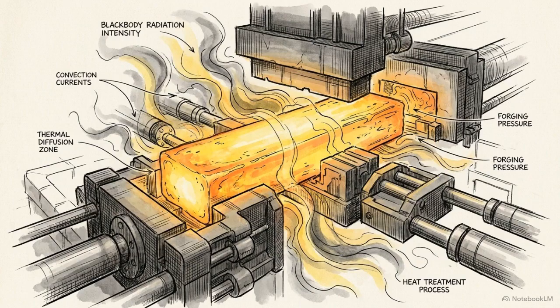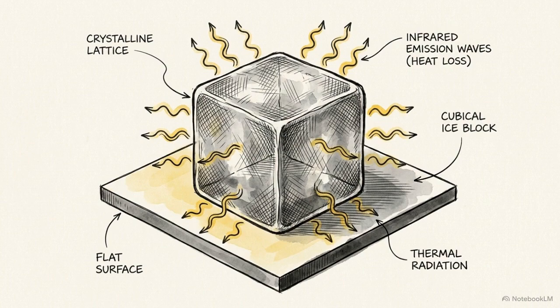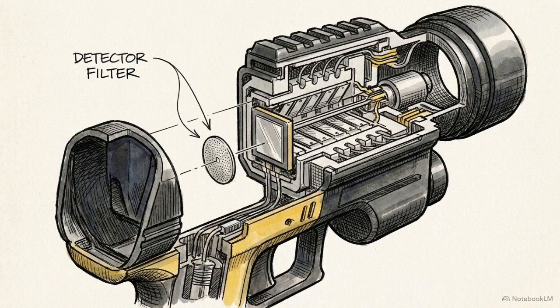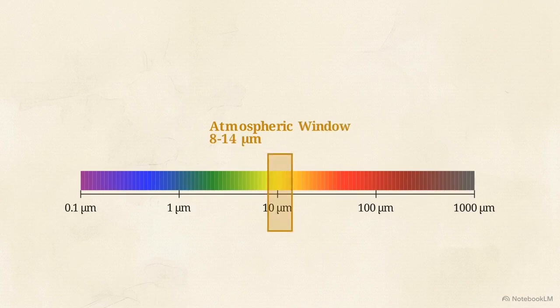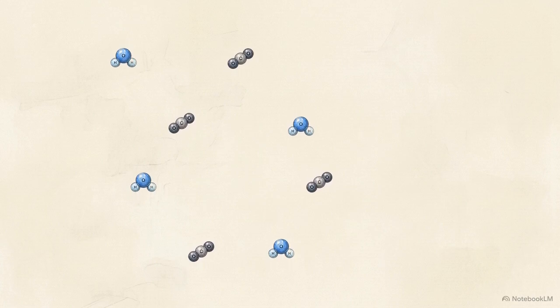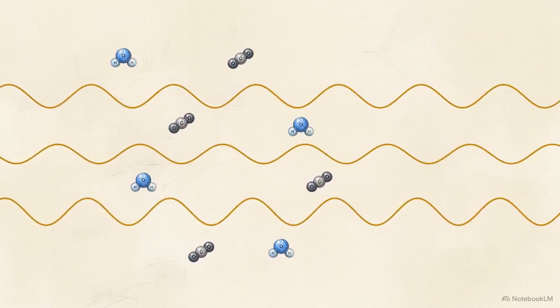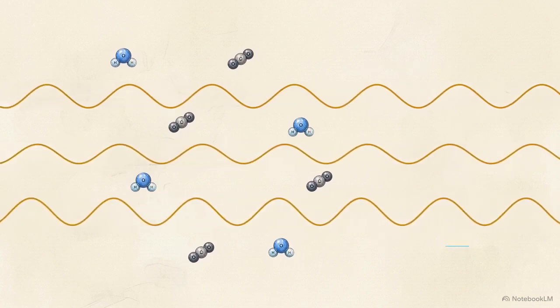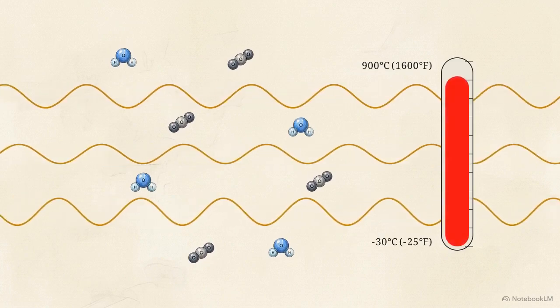At the sensor level, measuring that precise targeted zone requires strict adherence to the laws of thermodynamics, specifically the principles of black-body radiation. All objects above absolute zero emit electromagnetic radiation. To capture this, the MX6 utilizes a specialized thermopile detector calibrated to isolate thermal wavelengths strictly between 8 and 14 micrometers. This electromagnetic spectrum chart highlights the 8 to 14 micrometer atmospheric window. In this long-wave region, water vapor and carbon dioxide don't scatter infrared radiation. This lack of attenuation allows the hardware to calculate extreme temperatures from -30 to 900 degrees Celsius.